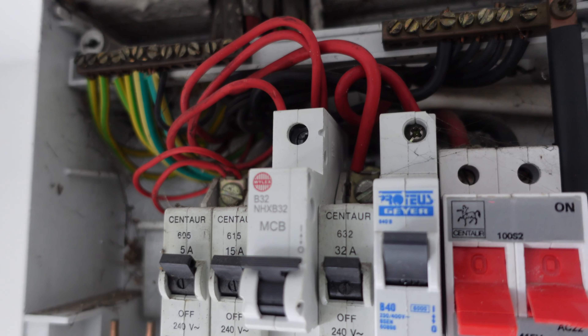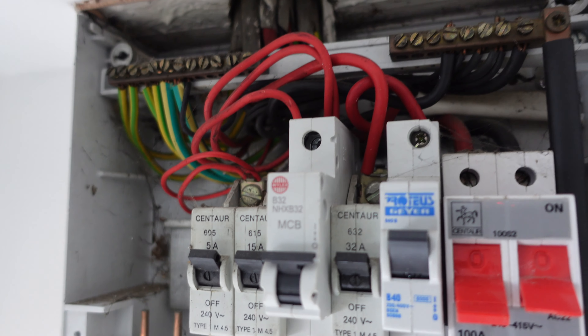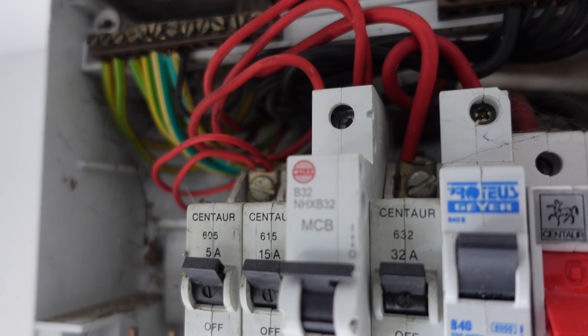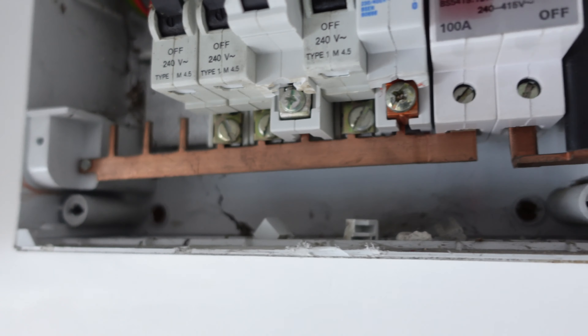Boxing's off, covers off — does not look too bad to be fair, the wiring doesn't. Bit of a shame there's one coming in here but I'll have to just wiggle it about. But look at this — they've even snapped the heads off the breakers so they fit in. That really is rough. That clearly hasn't been tested, has it? Because anyone who'd see that would see that it's dangerous with that hole in the front.